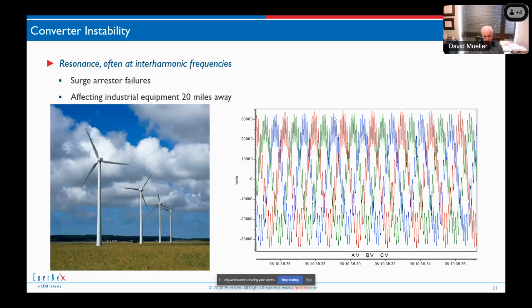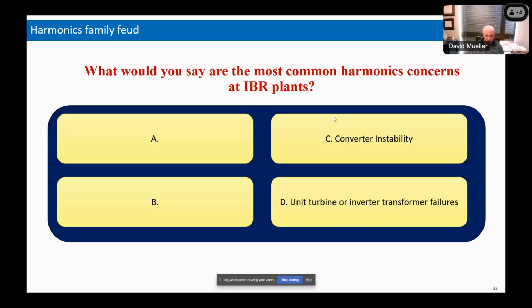What's going on here is that the controls are unstable at a frequency that the grid is resonant to. If we switch a capacitor bank in and we create this resonance, we'll get this phenomenon. If we take that capacitor bank out, this problem will go away because we no longer have a resonance at that instability. So the two things have to line up. The converter instability has to line up with the system resonance condition. All right, getting on to the third one.